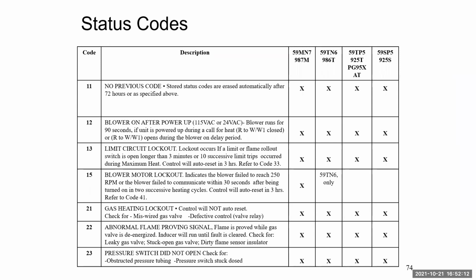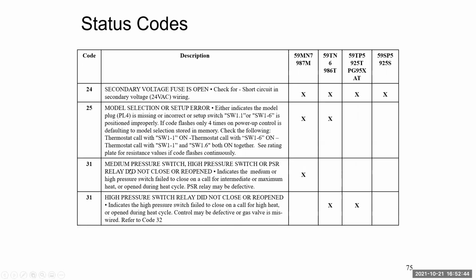Fault codes, they're pretty standard across the board. There's a few differences here and there. Big thing though, know which flashes first, fast or slow. Fast first, slow second. And that's critical, especially when you get into your double codes like 13s and 31s. Which one do we really have? And that's going to be a big difference. If we look here, 13's a limit lockout. We look here, 31's a pressure switch problem. So which one are you really chasing after?